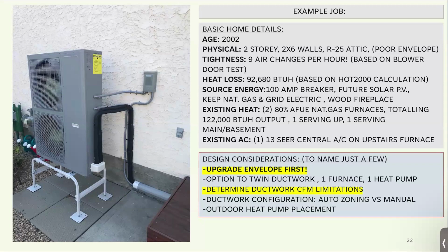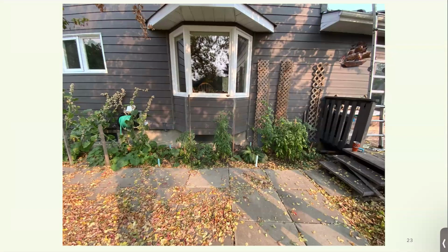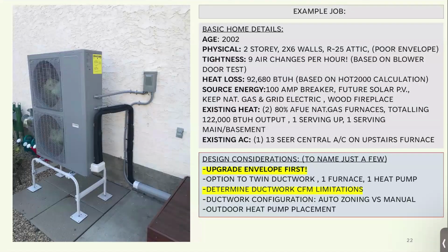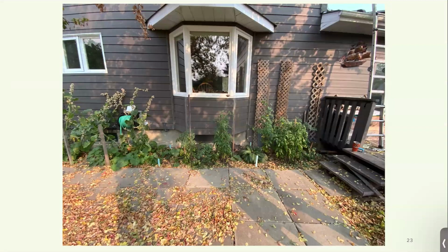I just did another one quickly because this is another scenario where it's challenging, because he wanted to put the heat pumps in the backyard, where this is a fully electric system, and actually these are going to produce a lot of ice because they do not shut off. Whereas this system, being gas hybrid, is going to run till about minus 10, I think in this instance. And then the balance point kind of lines up around there, and then the gas furnace would kick in. But in this instance, that electric based system is going to run that heat pump all year. So a lot of ice is created.